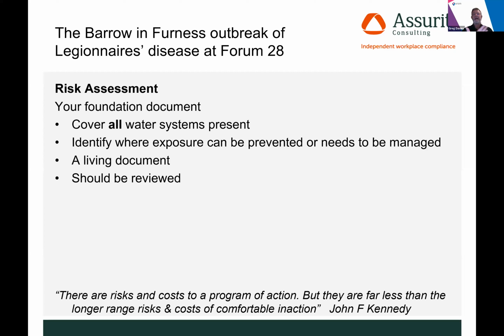But the 5 times you should have considered reviewing your risk assessment would be: changes to the system or systems within the building, changes to the use of the building, if greater information on controls comes out that could be applied, if you believe your scheme of control or your risk assessment were no longer valid, or a case of Legionellosis or Legionnaire's disease was identified from the system. So those were the requirements.